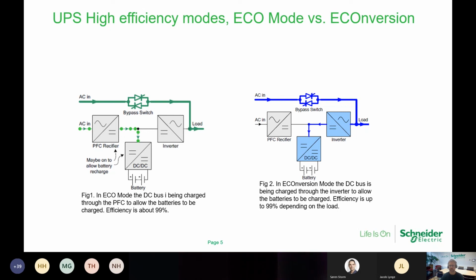Common for both high efficiency modes is that the static bypass switch is used for powering the load through the bypass part. The power loss is reduced, as the efficiency of the bypass part is around 98 to 99 percent. But that means that the load is more exposed to unconditioned utility power, and the UPS must then monitor the bypass power, react on events, and transfer back to inverter operation when needed.